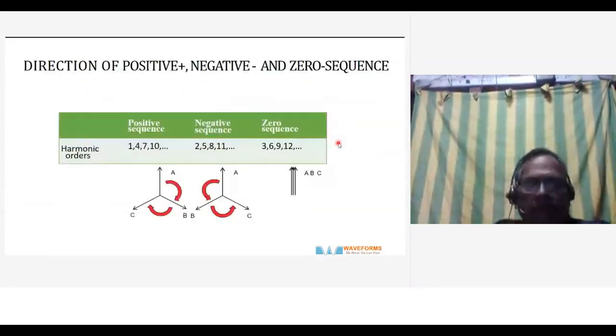So you just see the direction of it. Normally each phase is separated by a 120-degree phase shift, so normally they cancel out at the neutral and it is zero. But when it comes to neutral current, you see them adding up. You see them adding up to the neutral.